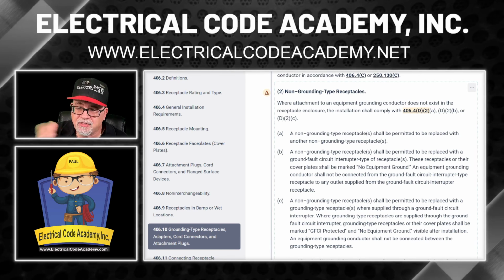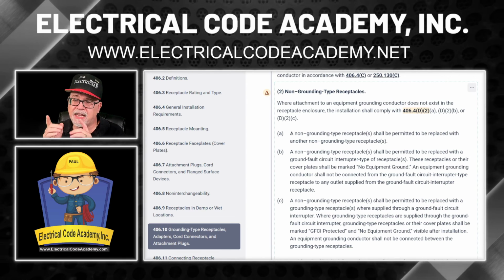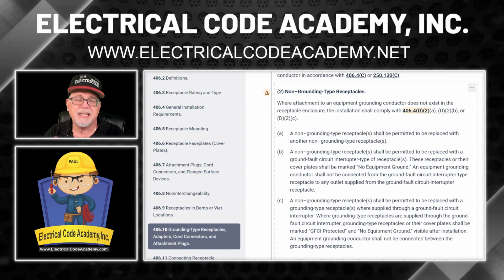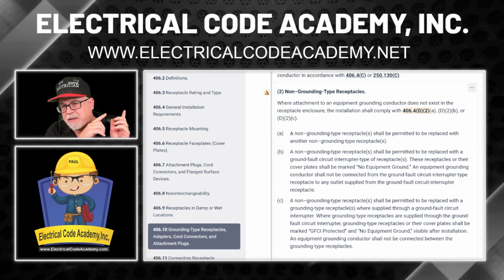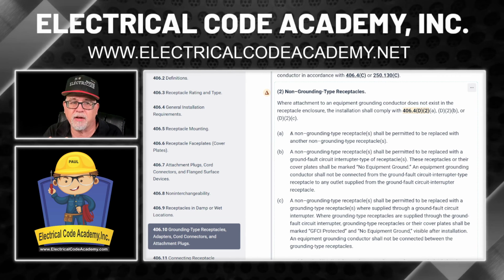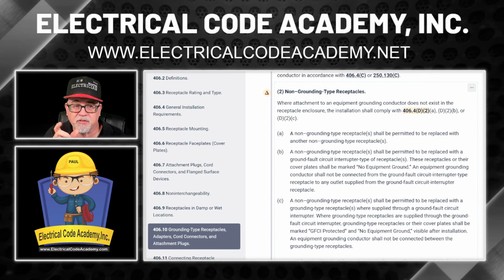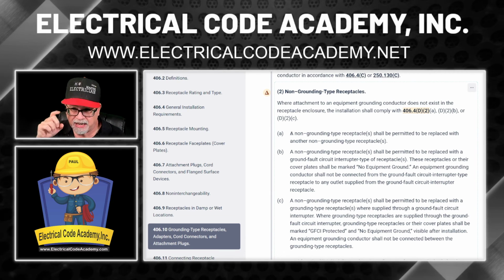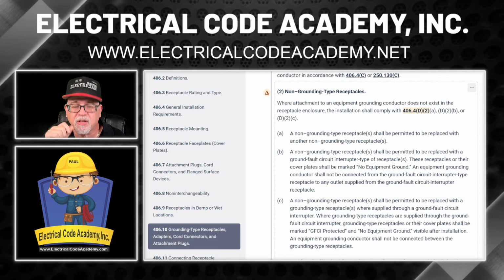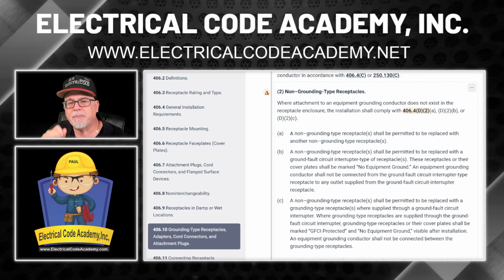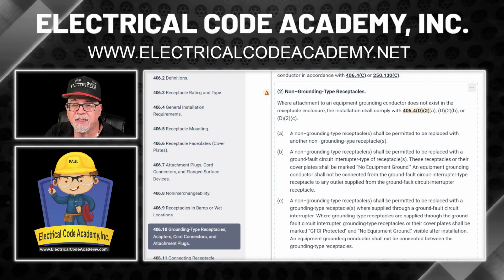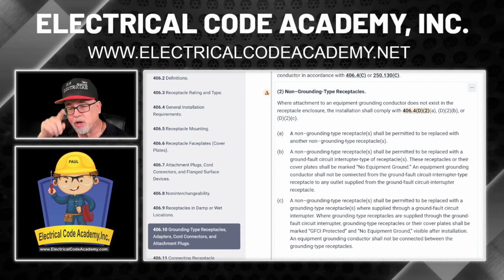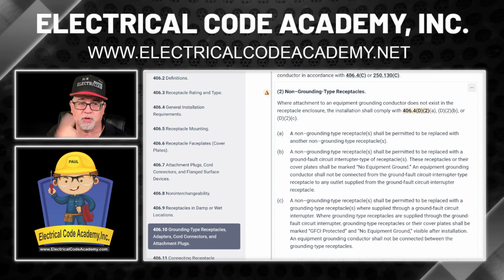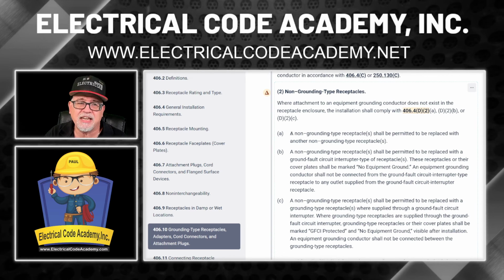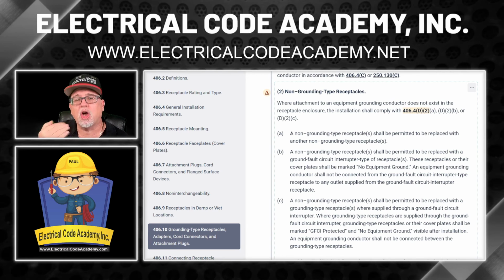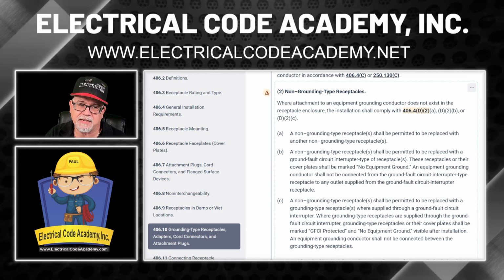Now, in his case, it also means that if he had to put that GFCI receptacle in the first receptacle location that's being supplied from the panel, that's the first outlet location, an outlet being the box, not the device, not the GFCI, that's a device. It goes in that outlet box. If that's the location and I put my GFCI receptacle there, then every receptacle that might be on the load side downstream, if I'm doing the rest of the room, those would also be GFCI protected because they're coming out of the load side of that GFCI device.